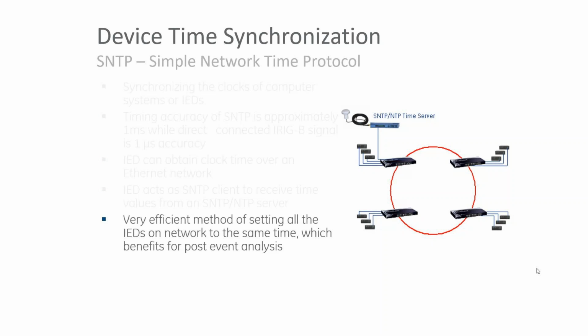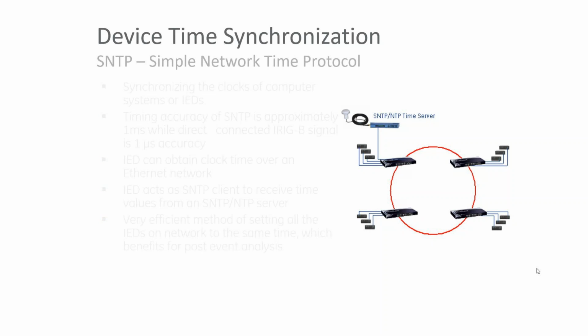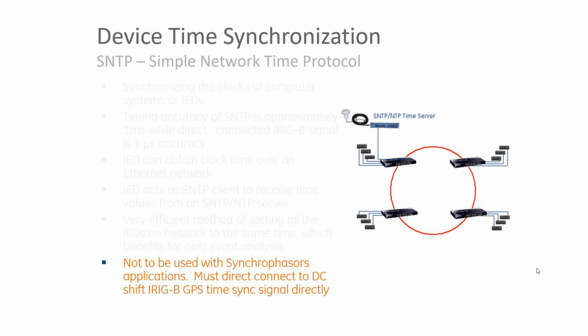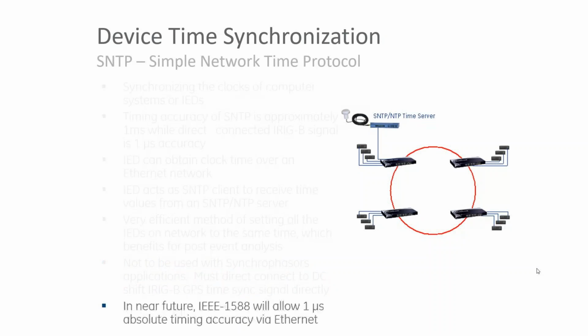The drawback of using SNTP is accuracy, it could be off by a couple of milliseconds depending on the clock or server used, which for applications like synchrophasors isn't good enough. Process bus is not good enough either. So you need something with microsecond accuracy for those applications.